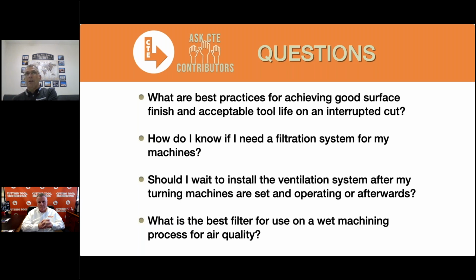Once that lofted fiberglass becomes saturated, when a mist droplet hits it, another droplet comes off the backside, so its efficiency greatly degrades once it becomes saturated. A coalescing filter, nearly HEPA quality, not quite, but nearly, loves lots of liquid. So once it becomes saturated, it starts to drain that coolant from the fibers and stays as efficient as it was when it was brand new.